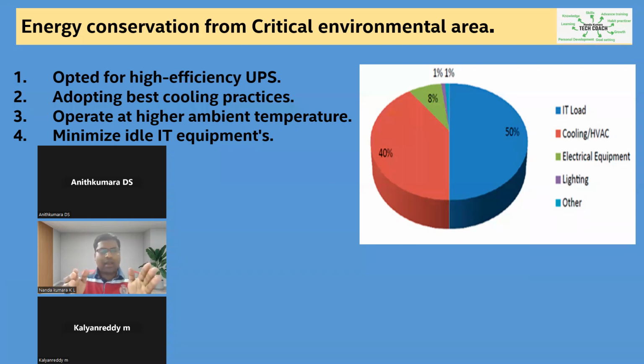Even if you have DX mode air conditioning units or precision units, you can straight away recommend dual fluid units, both chilled water as well as DX mode. So that will have a backup unit. For general operations, chilled water mode will be operated. In case chilled water is not available, then DX mode will come into the picture, so that you will have energy efficient PAC units as well as a backup. With that air conditioning system, we can reduce at least 6 to 8% of energy.